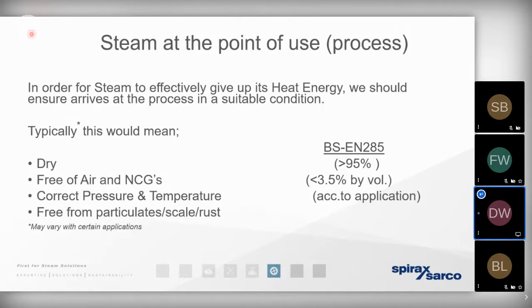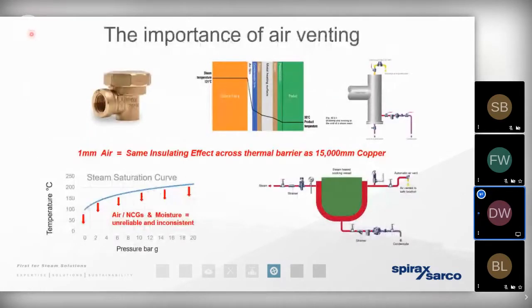There are also going to be benefits in ensuring that there's very little air and other non-condensable gases present in the steam, all of which steam traps can assist with. So certain high-end processors are going to have a greater requirement or a greater degree of criticality when it comes to steam trapping. And that's typically governed by a standard referred to as BS EN 285. So you'll notice there that air venting is also mentioned as a significant problem in a steam distribution network if we fail to vent that air away.